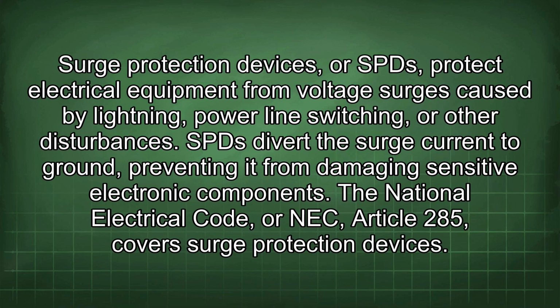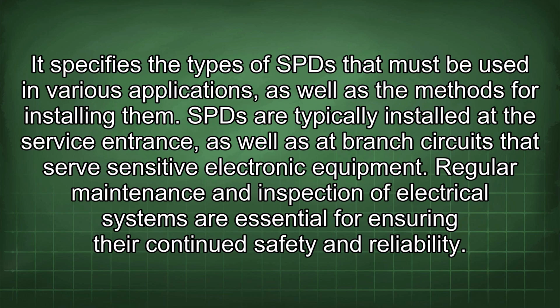Surge protection devices, or SPDs, protect electrical equipment from voltage surges caused by lightning, power line switching, or other disturbances. SPDs divert the surge current to ground, preventing it from damaging sensitive electronic components. The National Electrical Code, or NEC, Article 285, covers surge protection devices. It specifies the types of SPD that must be used in various applications, as well as the methods for installing them. SPDs are typically installed at the service entrance, as well as at branch circuits that serve sensitive electronic equipment.